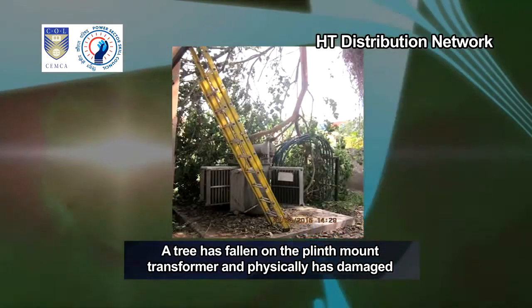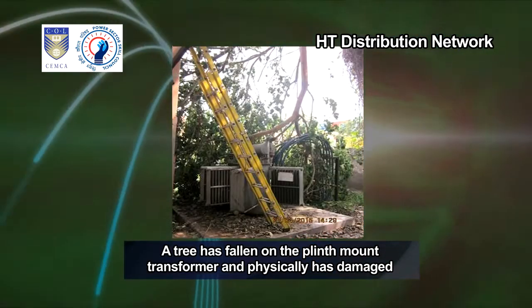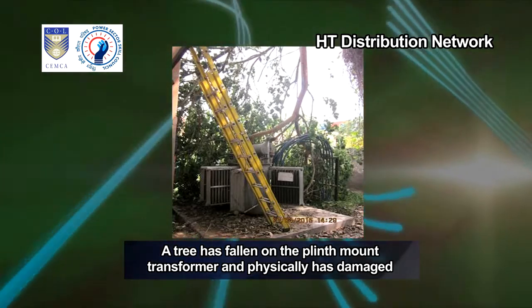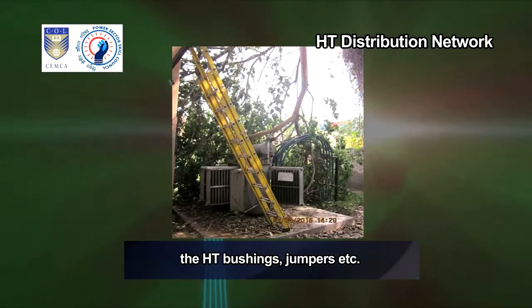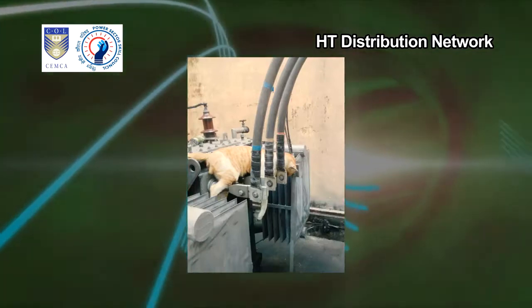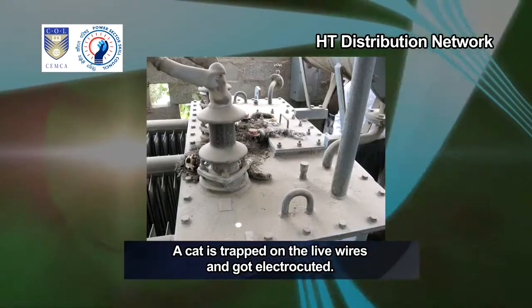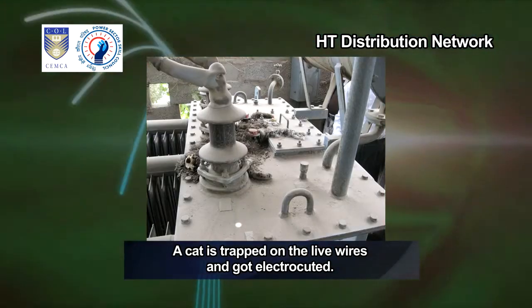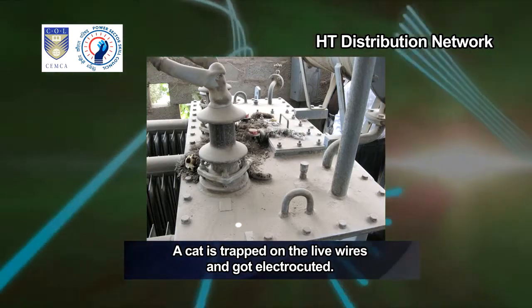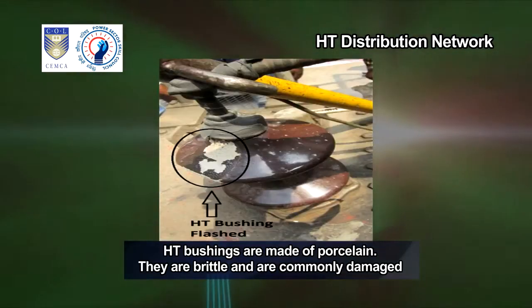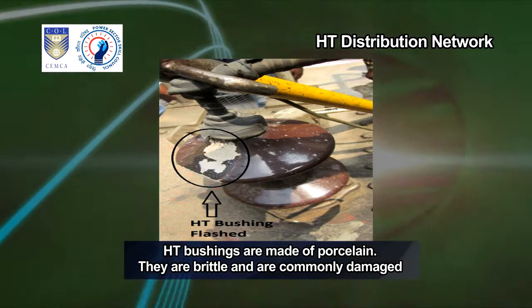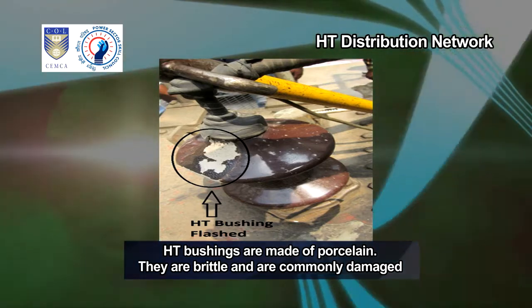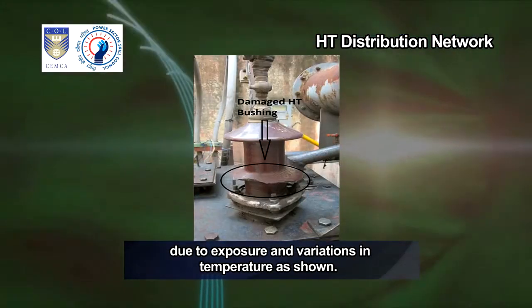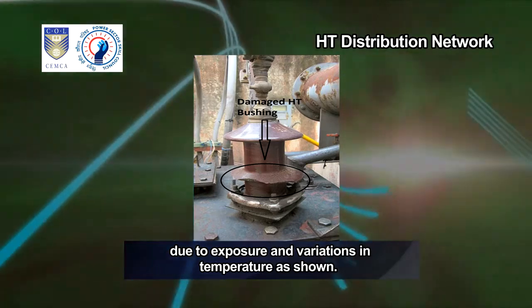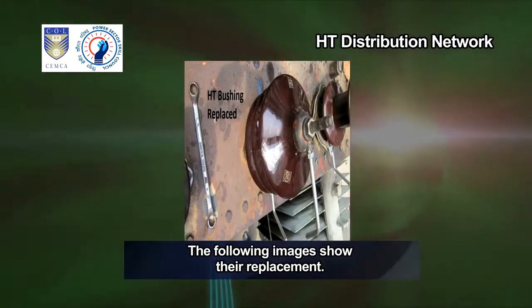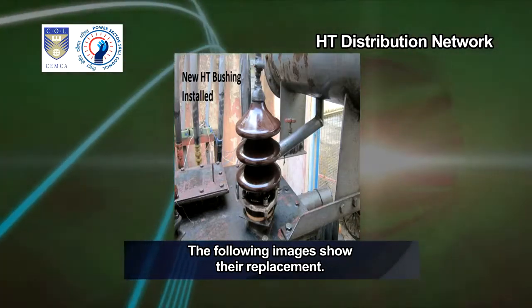A tree has fallen on the plinth mount transformer and physically has damaged the HT bushings, jumpers, etc. A cat is trapped on the live wires and got electrocuted. HT bushings are made of porcelain. They are brittle and are commonly damaged due to exposure and variations in temperature as shown. The following images show their replacement.